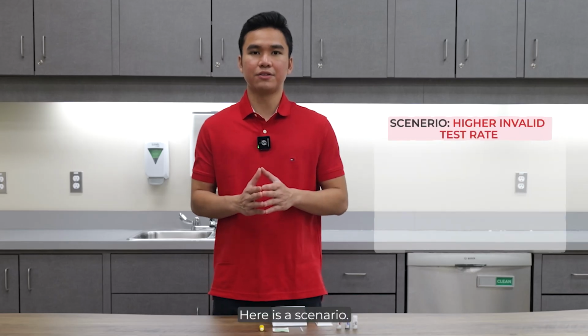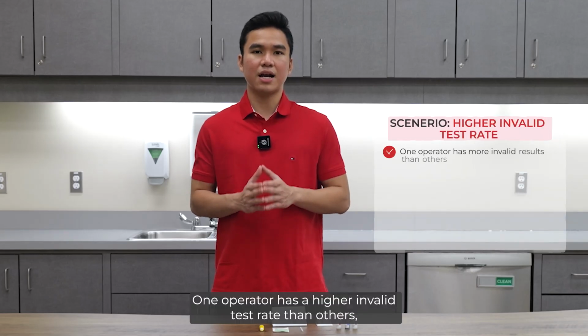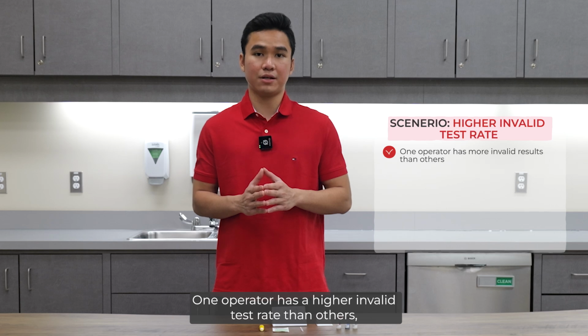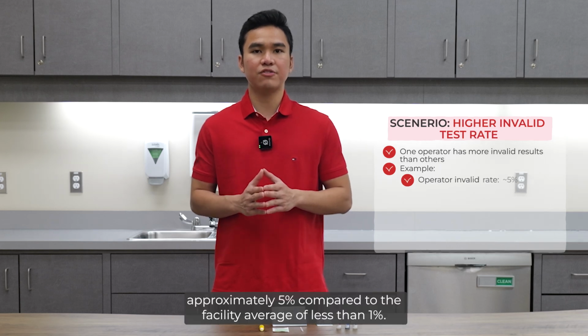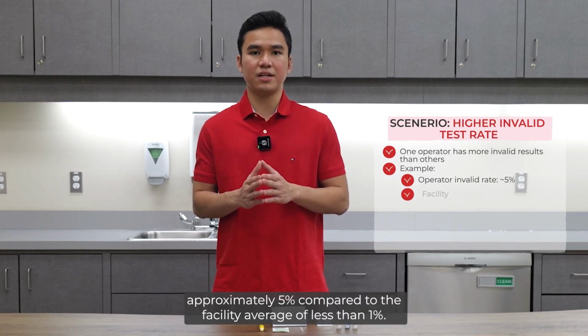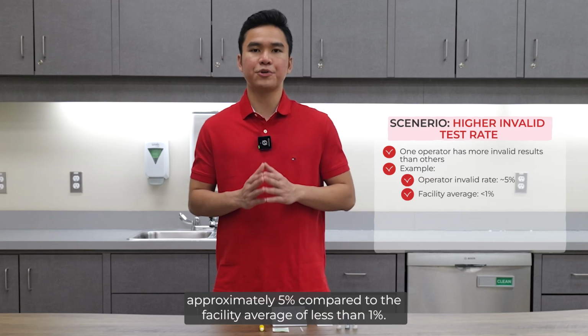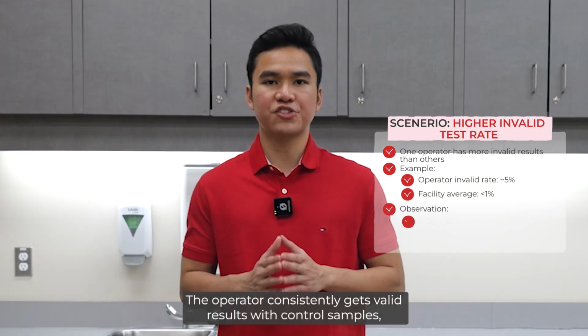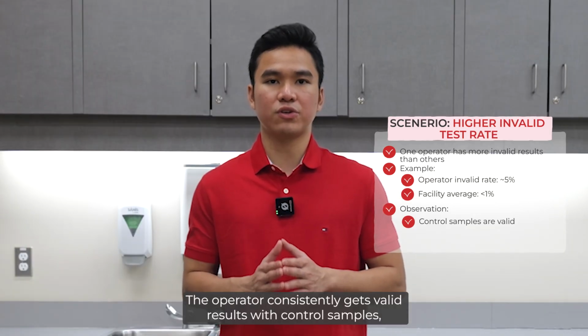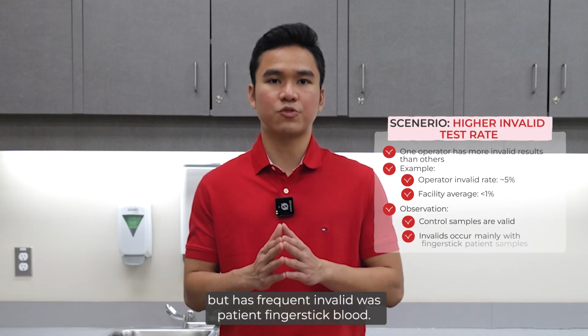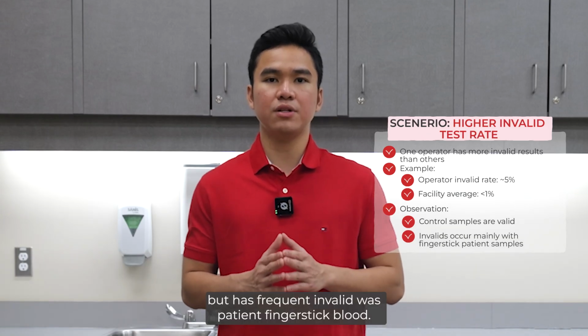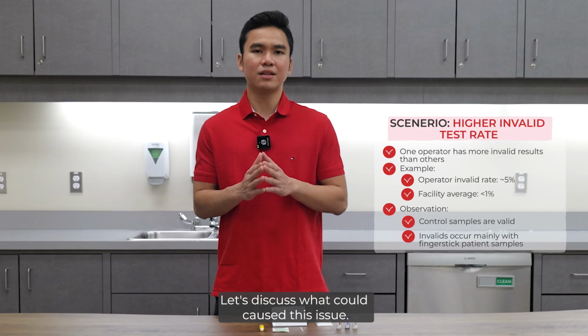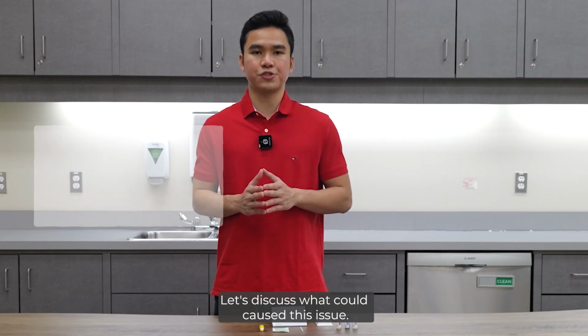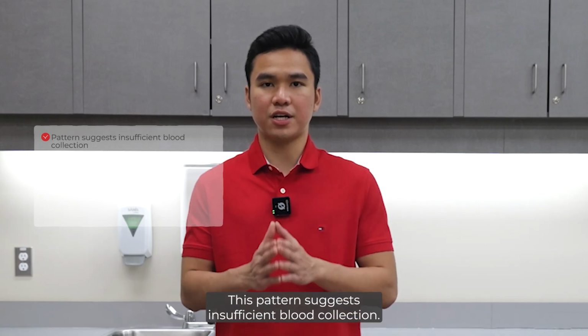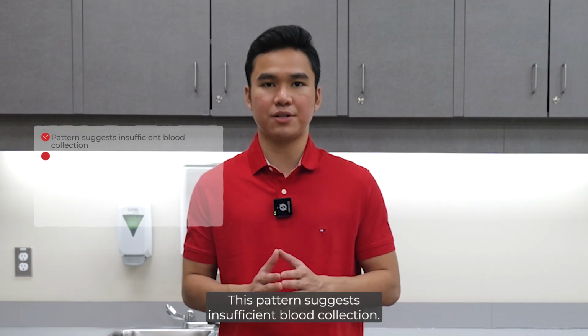Here is a scenario. One operator has a higher invalid test rate than others, approximately 5% compared to the facility average of less than 1%. The operator consistently gets valid results with control samples, but has frequent invalids with patient fingerstick blood. Let's discuss what could cause this issue. This pattern suggests insufficient blood collection.